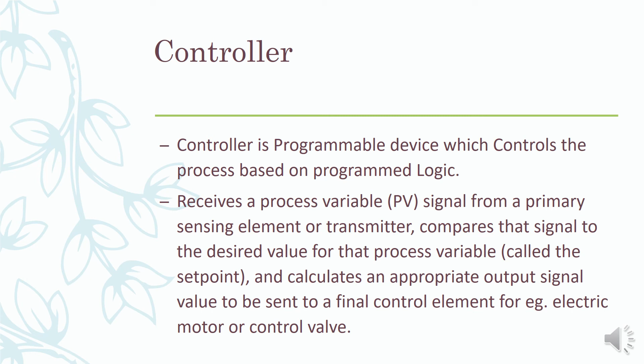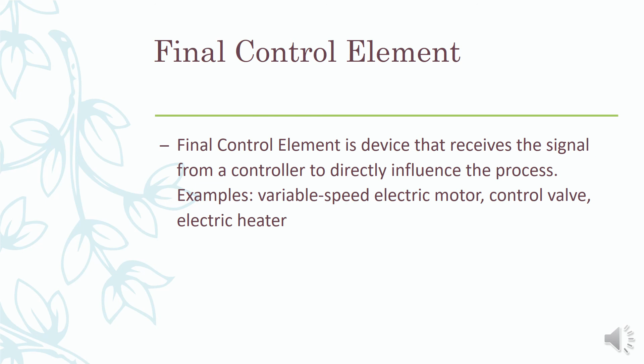Final control element. Final control element is the device that receives the signal from the controller to directly influence the process. Examples are variable speed electric motor or control valve or electric heater. As we already discussed, DCS first takes the input from the process and then it has a program logic, and based on the logic it will try to control the process, and to control the process it will normally control the control valve or variable speed electric motor or electric heater, so that it can change the flow, temperature, pressure, level, etc.